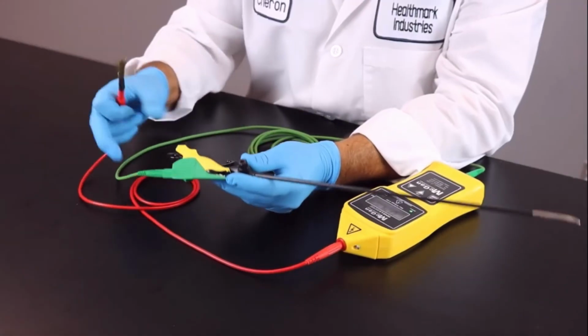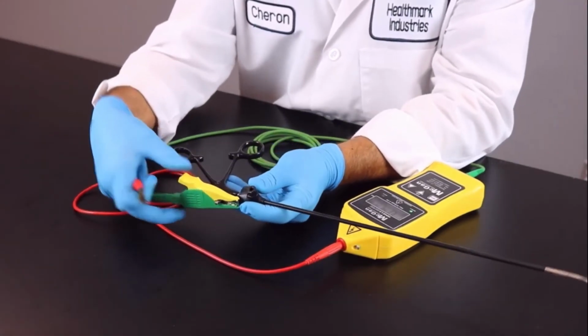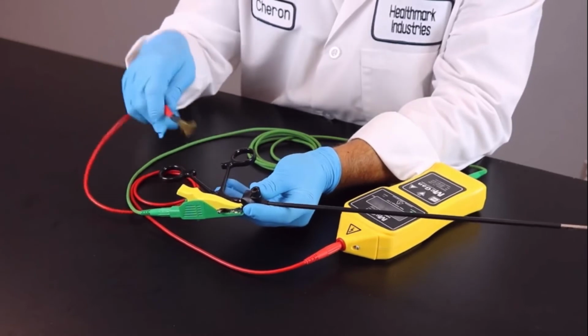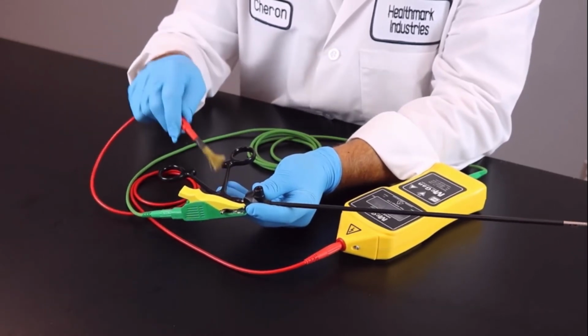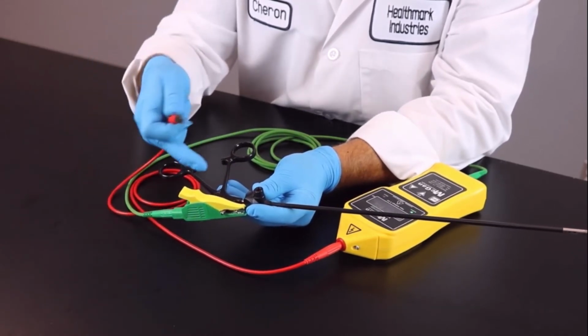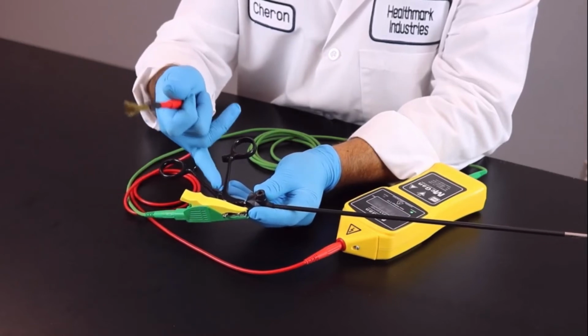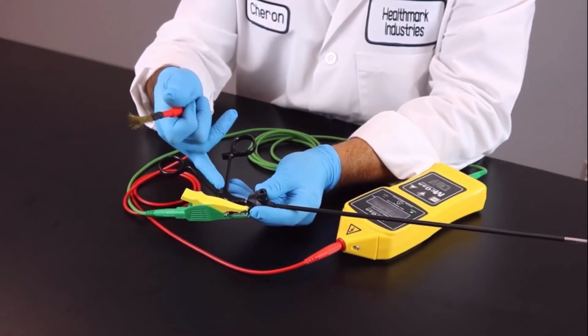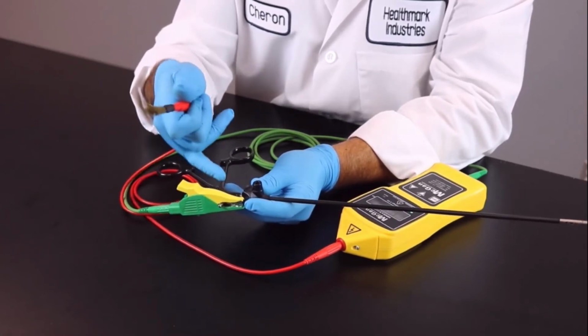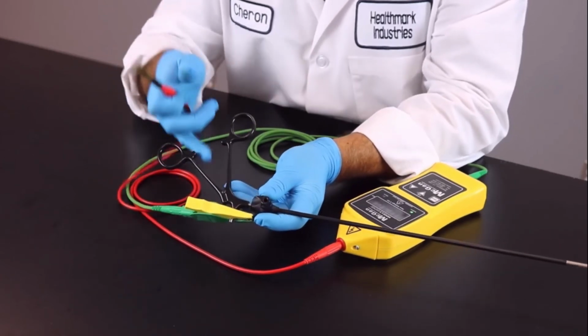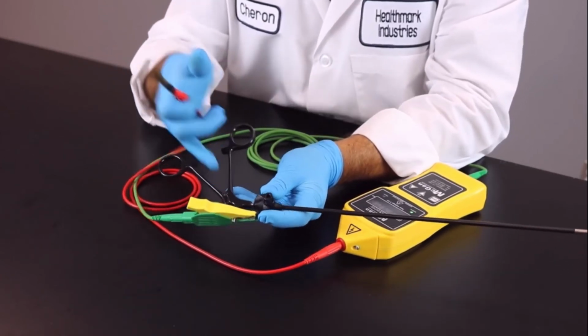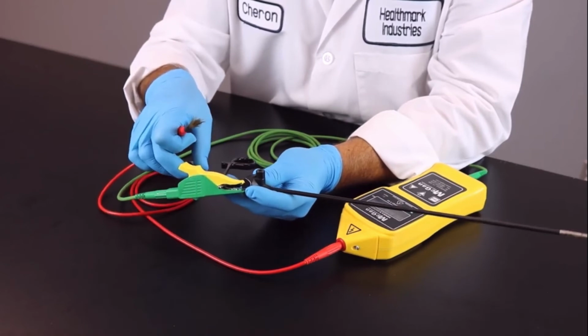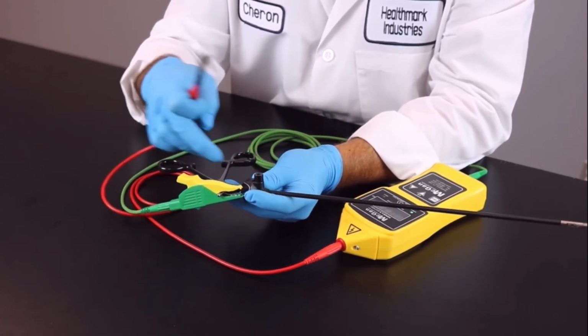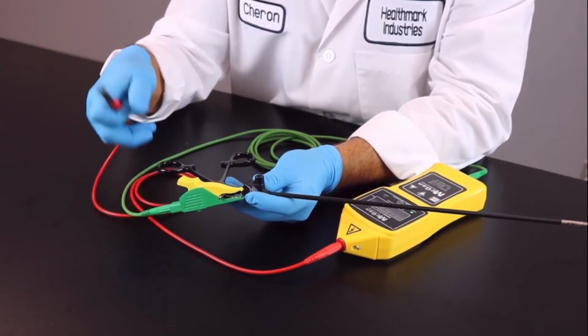Once you have that set, making sure that's securely grounded, you're going to brush, almost like painting, the handle itself. It will go off in the middle because you do have an exposure inside with the metal, which is normal. You will also have it deep inside in here depending on the model. So those 2 areas where the metal is exposed, that is supposed to be there. It's all the places where it's insulated.